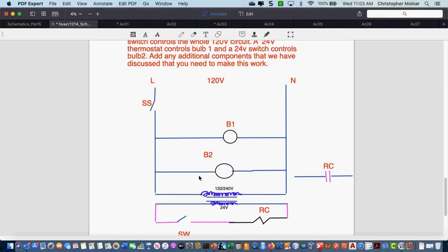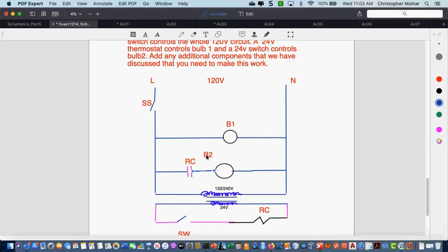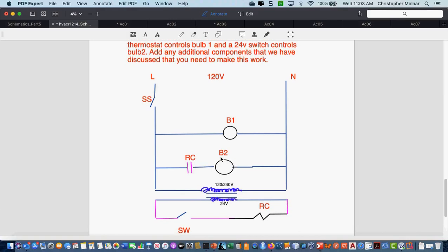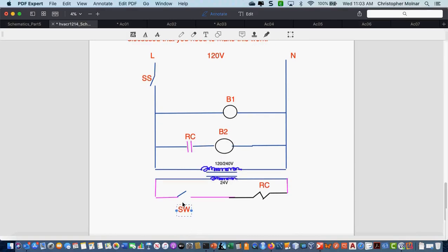Anybody? The contact? The contact, right? So if I take that line out, okay, now I have a single pole switch that's controlling bulb 2. Okay, now to control bulb 1, based on the directions, what do I need to add? Thermostat. Need to add a thermostat and there's something else. Another contactor. Yeah, another relay or contactor.